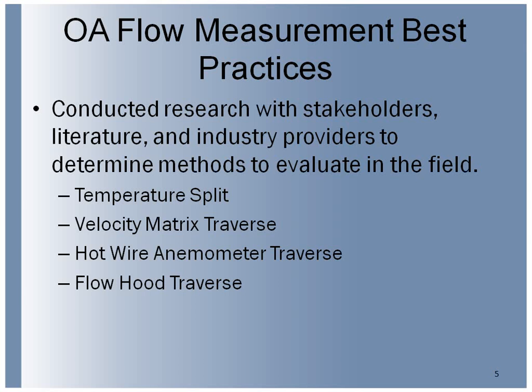The first thing we did was really try to make sure we were going to go to the field using best practices, and that we understood and had a good protocol for how we were going to do these measurements. So we worked with the TAB industry folks and all the good papers that have been written around flow measurement testing, then developed a methodology to do evaluation in the field for our purposes, since we were focused just on outside air flow testing, which has its own set of velocity profiles and things.